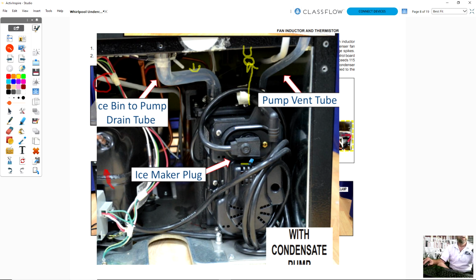So the newer ones now, they put a regular 120 volt outlet in the actual pump, and this plug that you're looking at is the regular ice maker plug running over here feeding the ice maker. So the ice maker plugs into your condensate pump, then your condensate pump plugs into the wall. So it still has a safety switch built in, so that if your condensate pump is full and is not draining, your ice maker will not run. So before you tear your whole ice machine apart, you want to check your condensate pump and make sure that it's not full and overflowing and leaking in the customer's home.